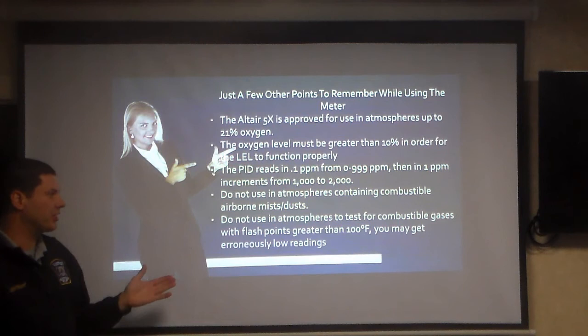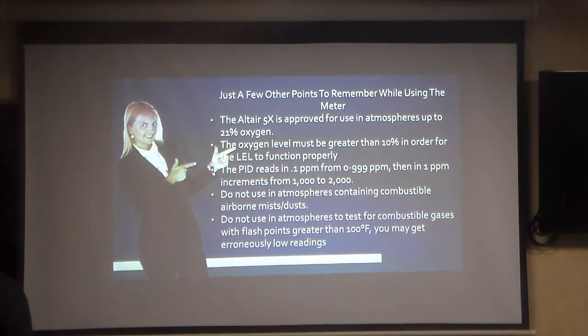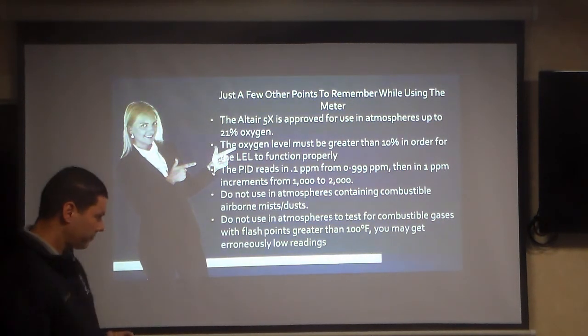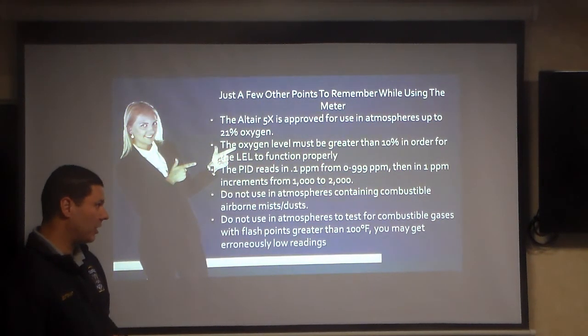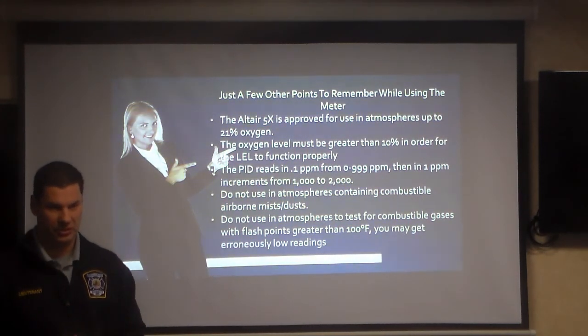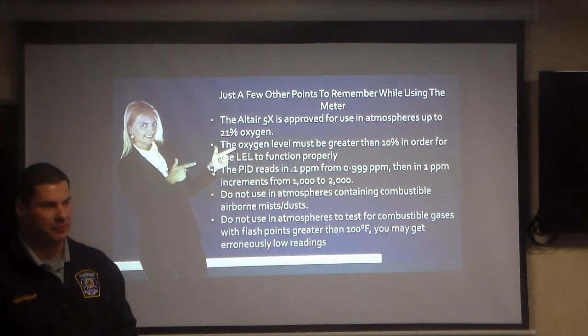Don't use them in atmospheres that contain combustible or airborne mists or dusts. That's the same for the Altair 4X, you shouldn't use those in that type of atmosphere. And don't use them for atmospheres with combustible gases that have a flash point greater than 100 degrees. It has a very difficult time. The LEL has a very difficult time identifying those types of chemicals.